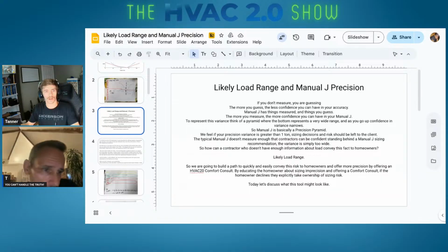Does your ductwork leak to outside? Does it leak to inside? Yes, duct leakage to outdoors, all these things play a huge role. When your system kicks on, does it go negative, or does it stay neutral or a little bit positive?